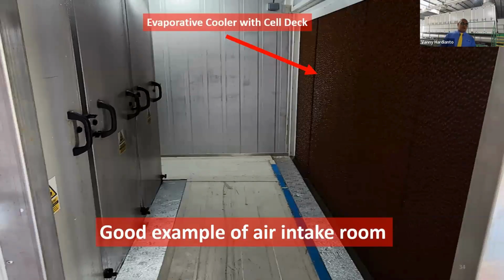I have seen a customer who also made an intake room and used a cell deck to cool down the temperature because the outside temperature is quite high. So they try to cool down the temperature before it enters the ventilation unit. But you should remember that if you use this kind of intake room with cell decks, it will produce more moisture. So your ventilation system will be doing a hard job to lower the humidity.